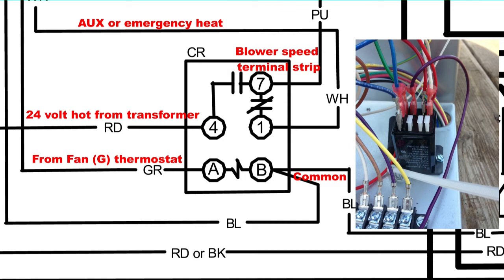So that means if you were to turn on your emergency heat, you would have a low voltage 24-volt signal travel down the WH wire and then directly to the blower. So the blower will come on if the heat strips are on. This is a little different tactic from their ARUF air handler, which uses high voltage to do that, but it'll still do the same. The downside to this is if your sequencer is stuck, it won't matter what control voltage you have—it'll just rely on the limits to protect it.